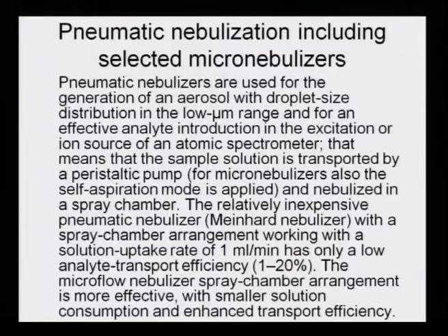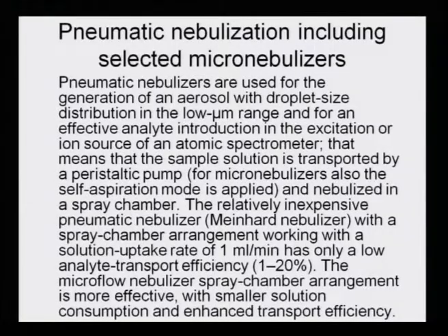So, it does pass the analyte slowly, and only 1 to 20% of the analyte is transported. The microflow nebulizer spray chamber arrangement is more effective, with smaller solution consumption and enhanced transport efficiency.